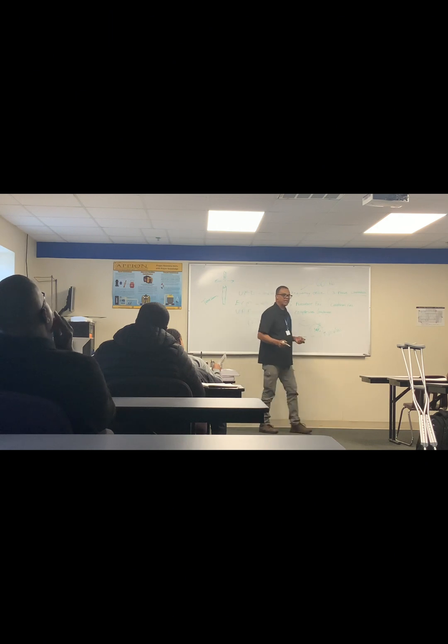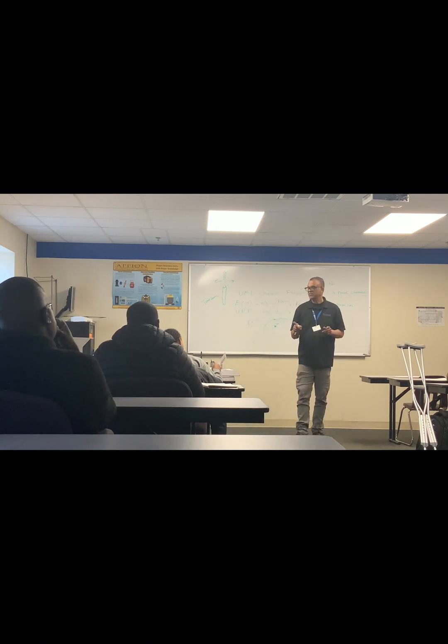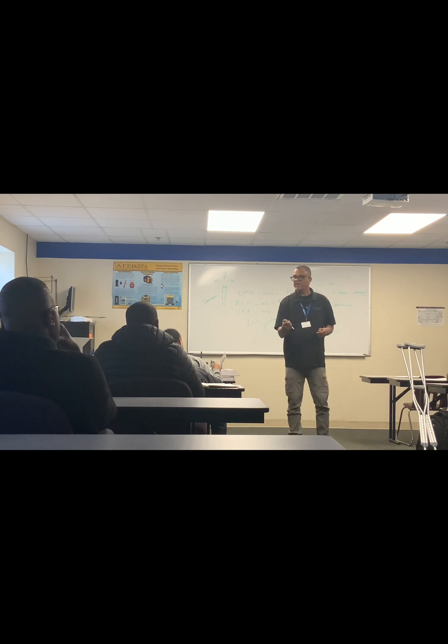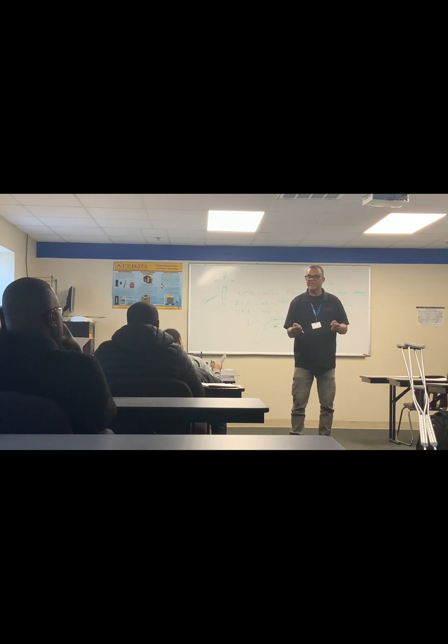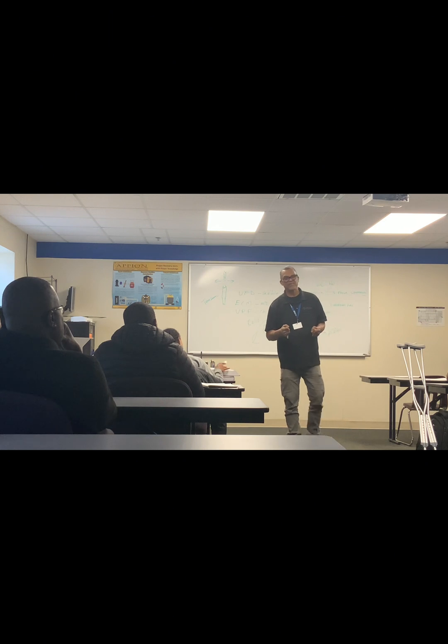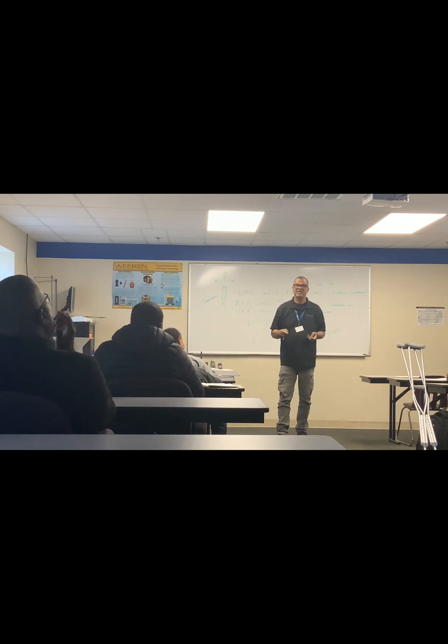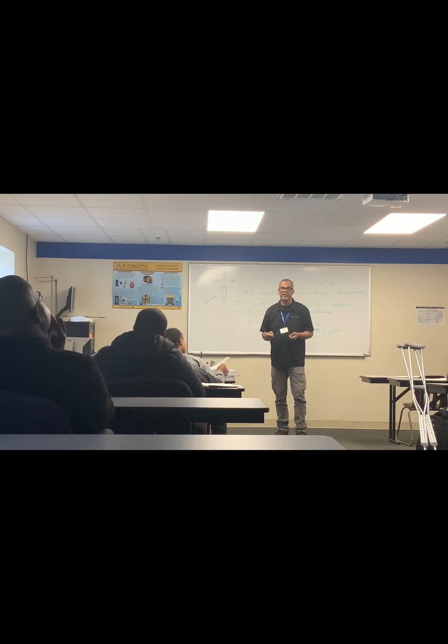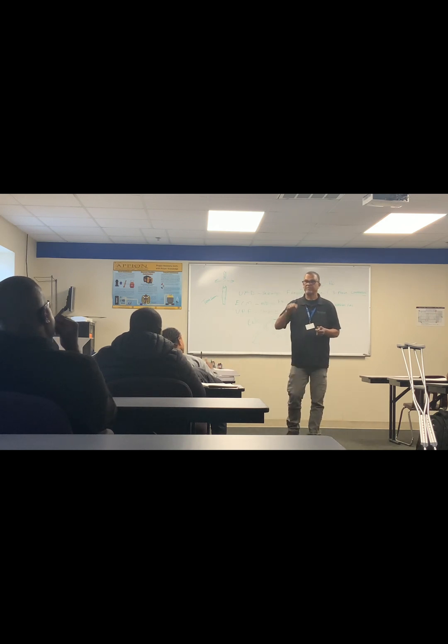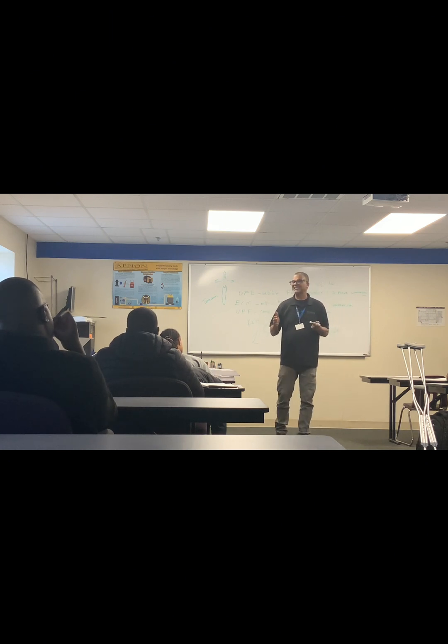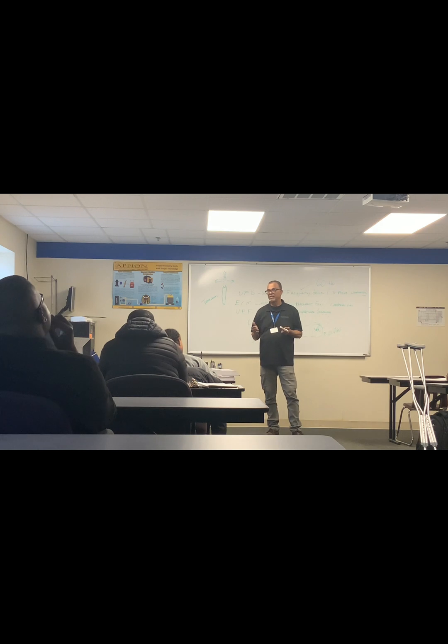9 out of 10 mechanics would probably say, I look at the amperage on the meter, I take my amp meter and I tighten it in the saddle and pull that belt tight until it falls into the numbers of the amperage of the motor. Not true, but 9 out of 10 techs that I know, that's the way they do motors. And there's another group that just pushes on it. Feels kind of tight, that feels kind of right. Well, how do you know that? Well, that's how I always did it, that's how I was taught. It doesn't mean that that belt is pulling and sitting on those pulleys in the correct manner.